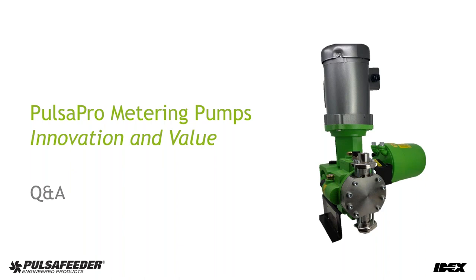The hydraulic bypass valve will operate. It's kind of dependent on the system conditions, the pressures that are involved, etc. I can tell you that if it goes on for an extended period of time, that hydraulic fluid will become entrained with gas again, so it can operate in that state for some time. As long as there's hydraulics in there, it'll be fine for a long period of time.